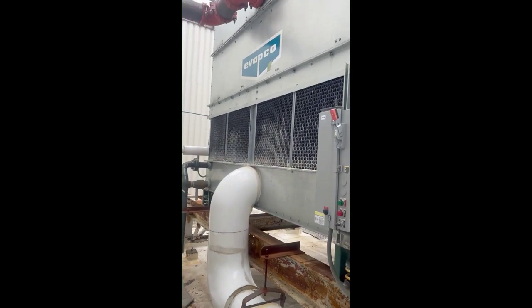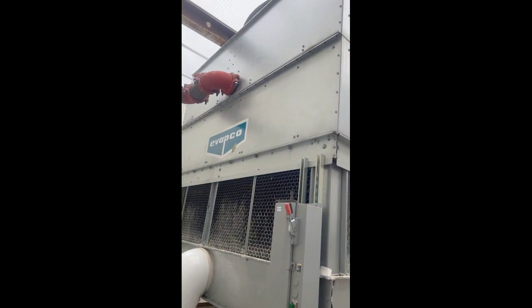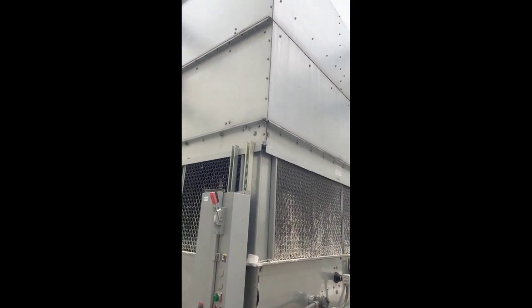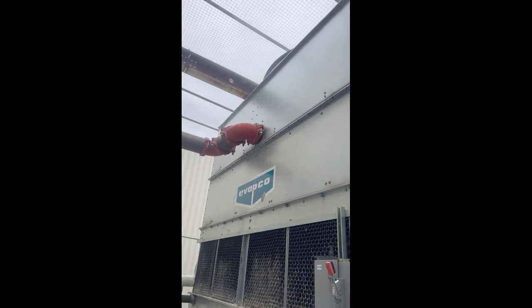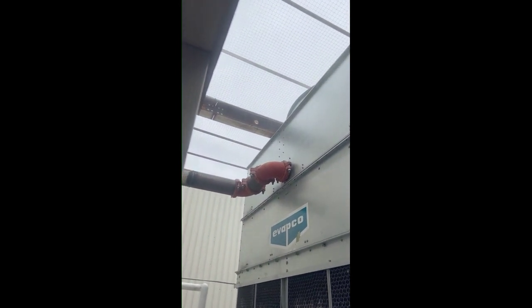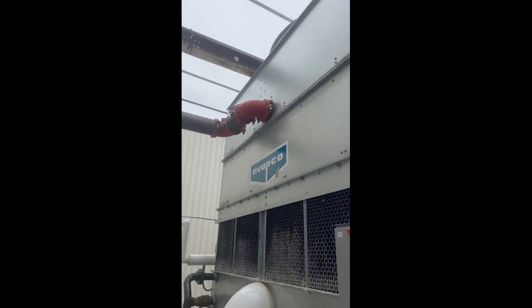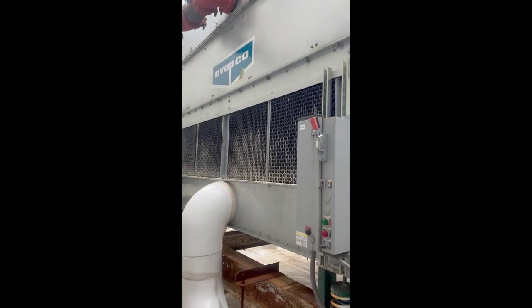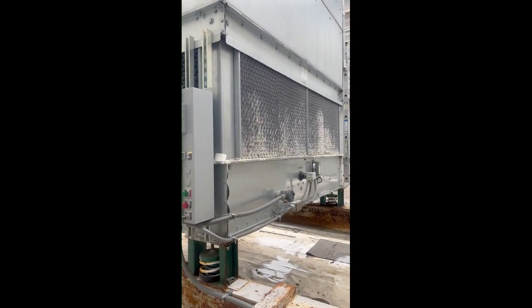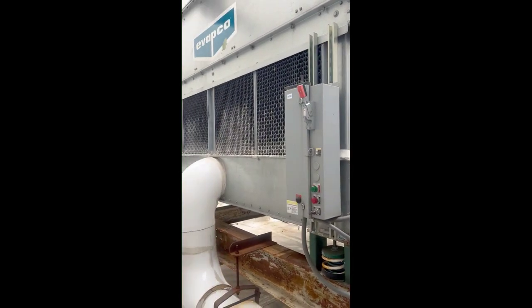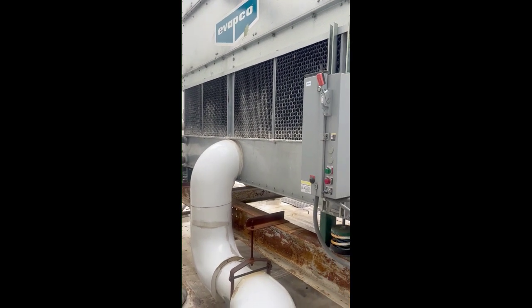This water tower is a heated sump. Heated sump means that in the wintertime, even if it's 10 below zero, this water will still be working in the hot. You can see the steam coming out from the hot water. This is what we use to cool for the air conditioning system. The scale that's here needs to be knocked down. This is due for cleaning. We'll show you a video on that.